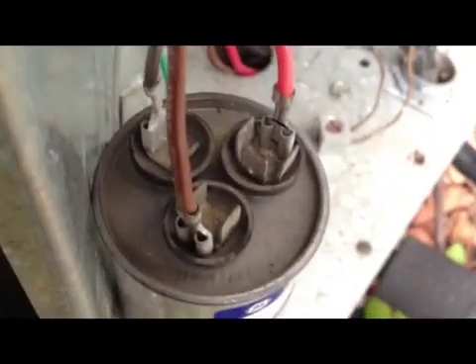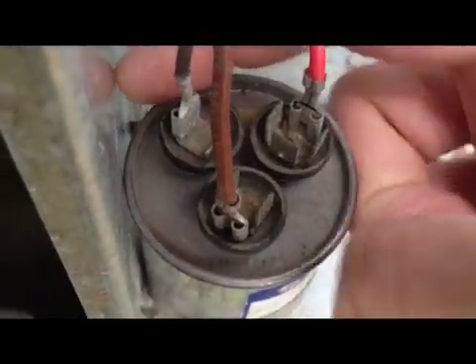The one that has all the prongs on top is the common, so we're going to connect the common to it. Then you're going to reconnect your fan on the fan terminal. The compressor terminal is labeled HERM — H-E-R-M. The other one is C, written on this one, that's for the common. And this one is fan. So: HERN, common, fan.